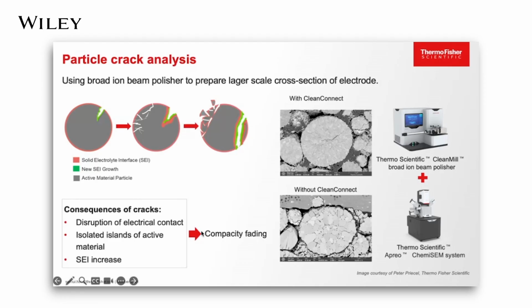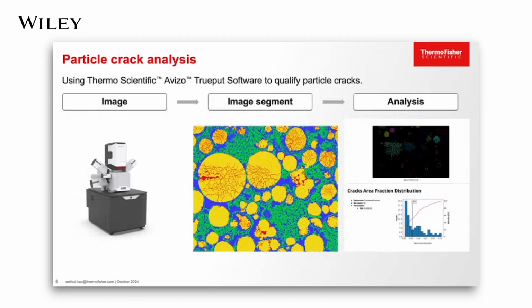Using the Thermo Fisher CleanMill broad ion beam, we can get a nicely prepared large cross-section of a cathode electrode without exposing it to air, thanks to our CleanConnect inert gas sample transfer system. Then we use the Thermo Fisher Apreo SEM for imaging the cracks in the cross-section with really excellent, fast imaging capability. Finally, we always want to know how many cracks there are across the cross-section of the electrode. However, it's always hard and sometimes boring for battery workers to analyze those cracks without an automated and statistical way. So the need is to do this kind of work in a fast, reliable, automated way to get the statistical result of cracks.